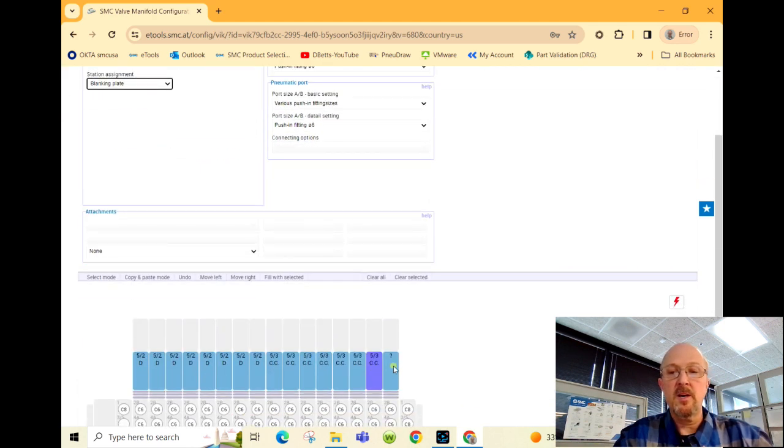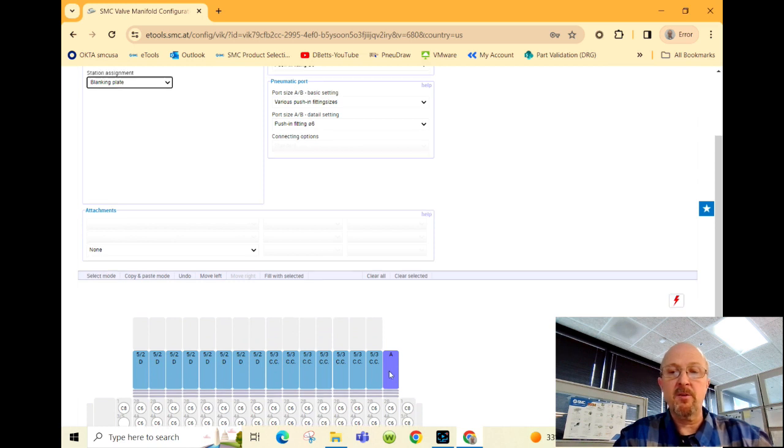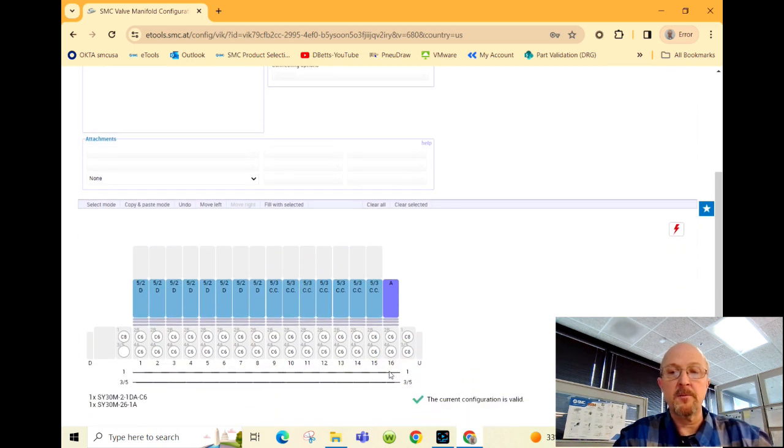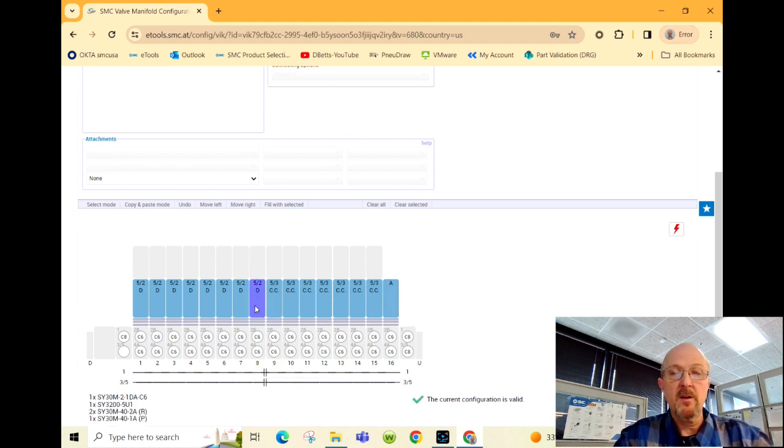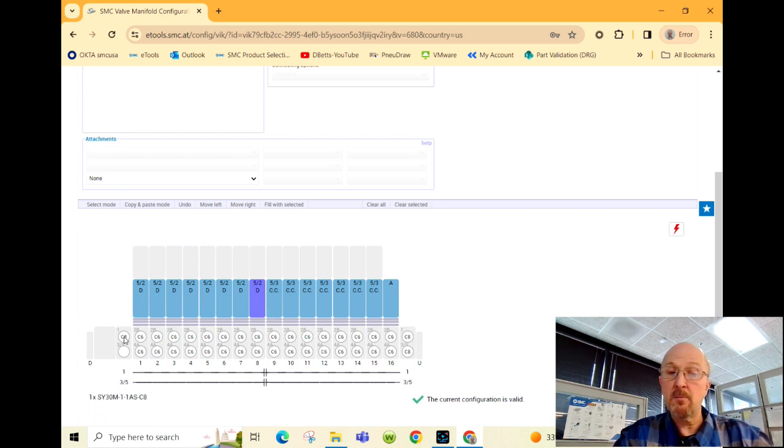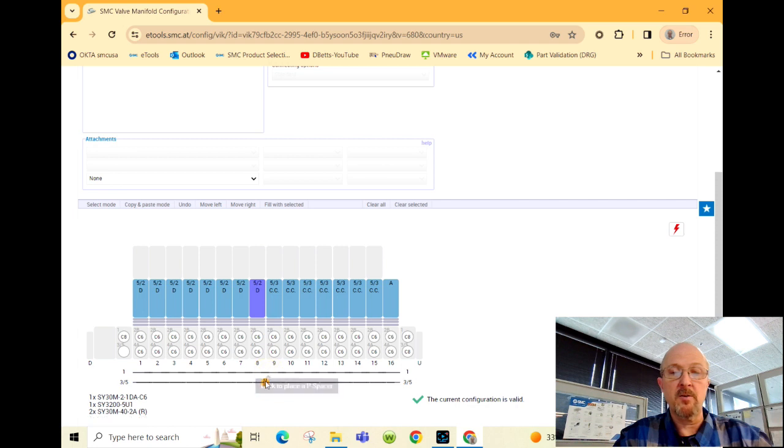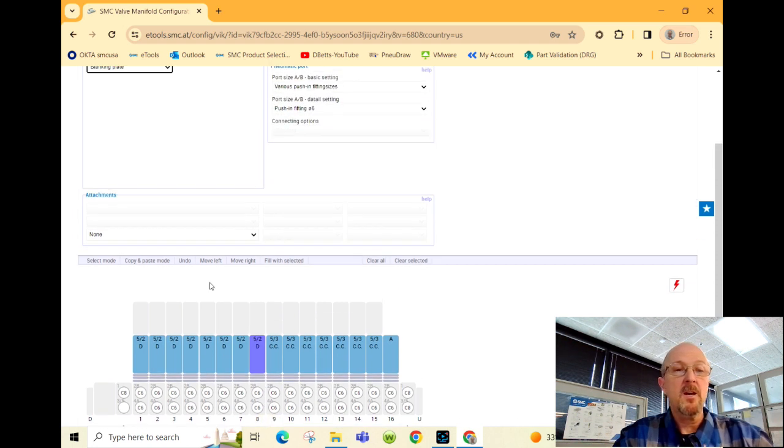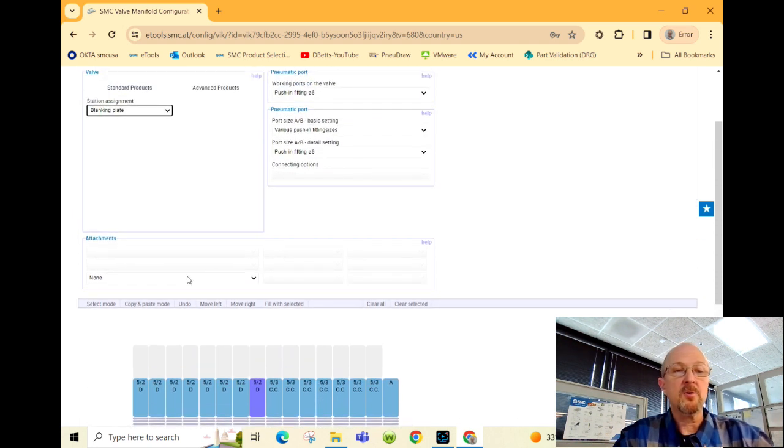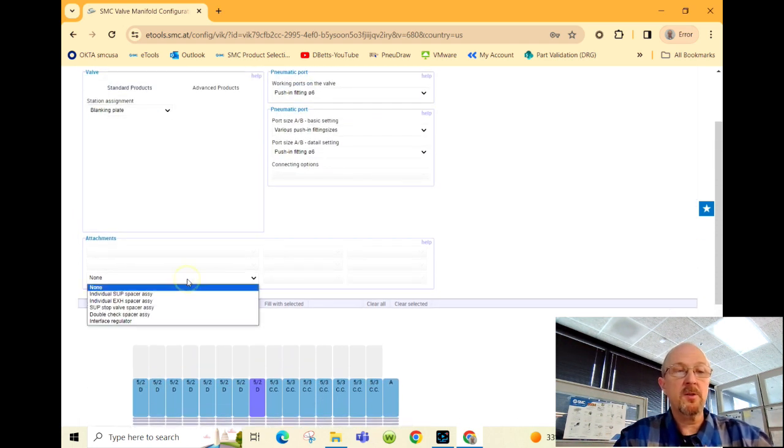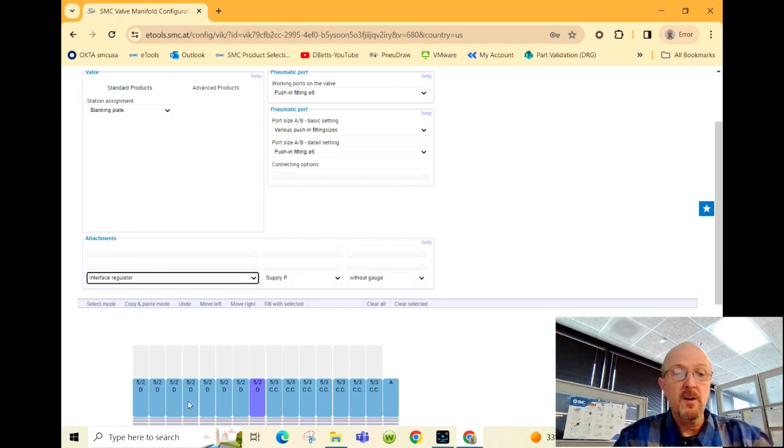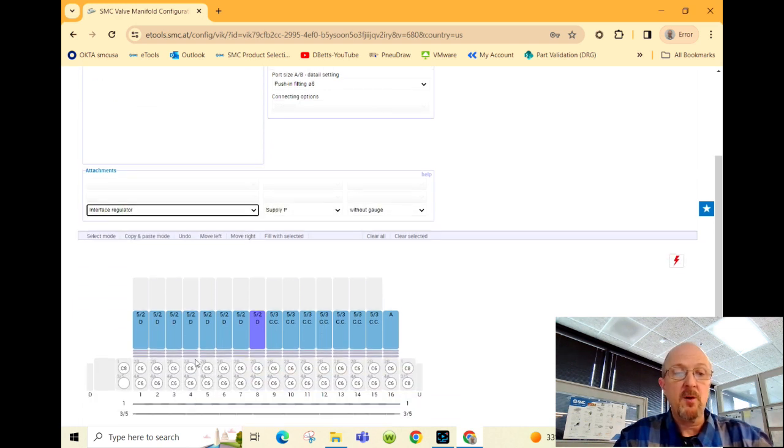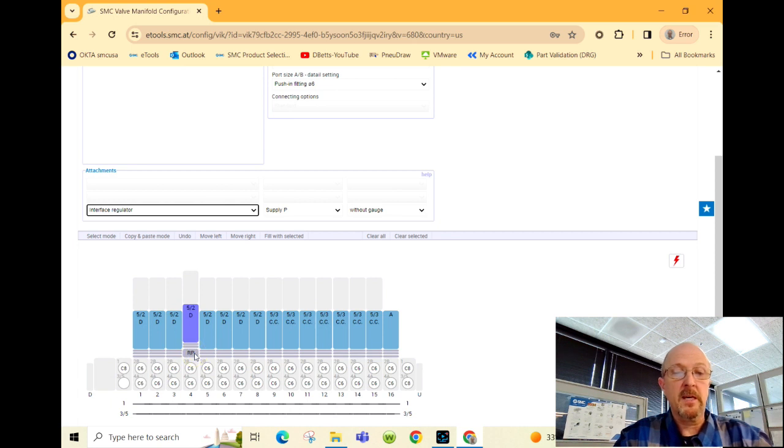If you happen to need a blocking disk between two valve positions, if you're bringing in different pressures to different end blocks, you can do that down here on the bottom. It also gives you the option of selecting an interface or a sandwich regulator, and that would be done by simply clicking on one of the spacer graphics right below the valve.